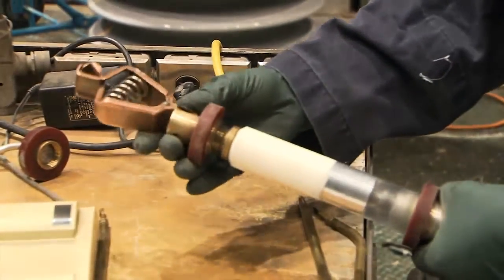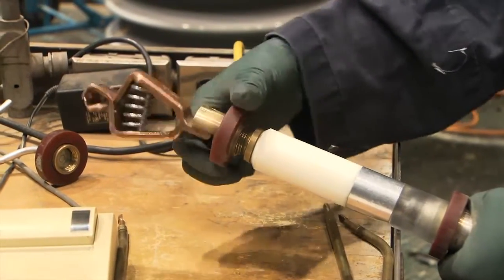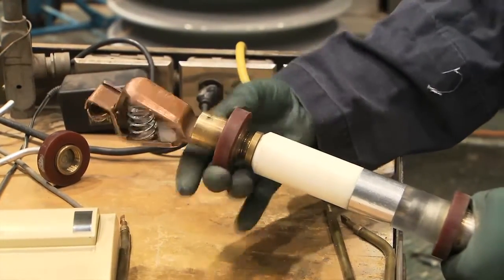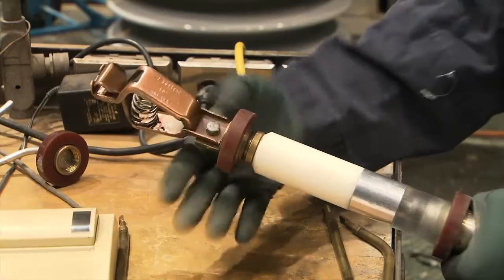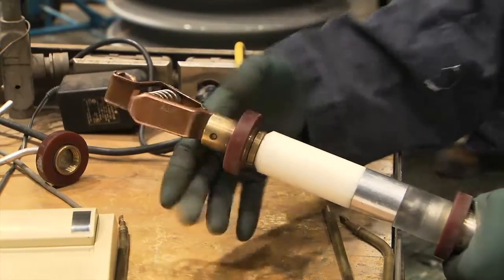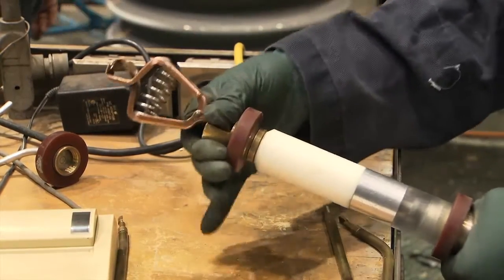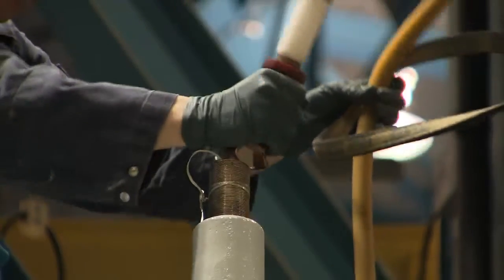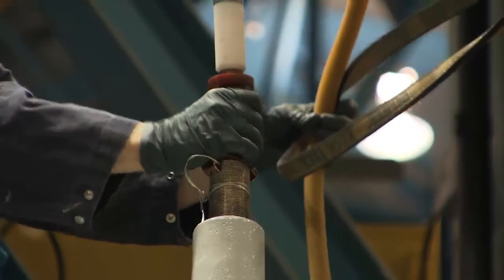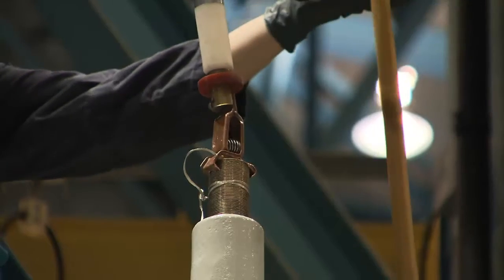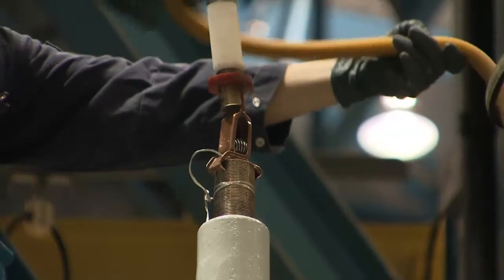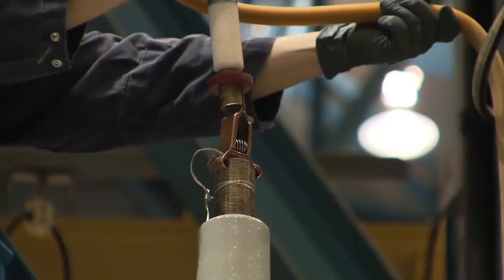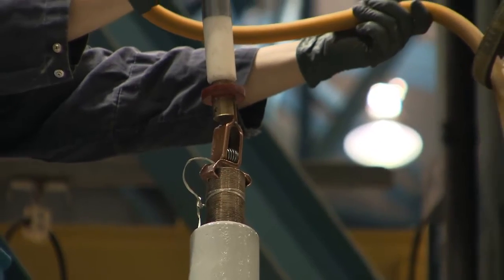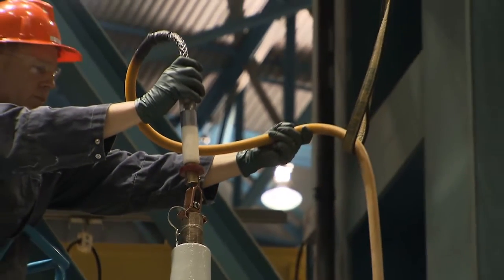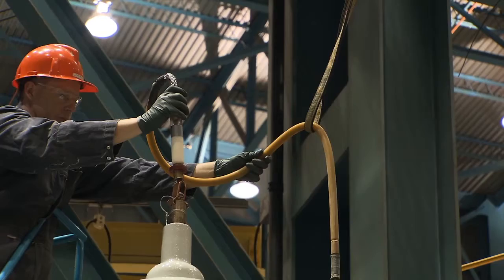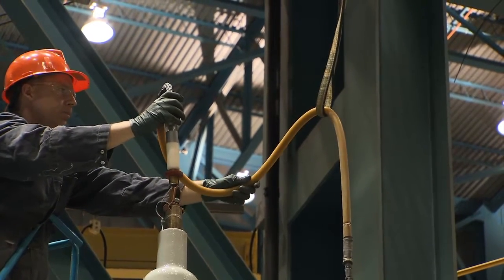Attach the connector clamp to the high voltage lead that will be connected to the top of the terminal. Connect the high voltage lead to the top of the terminal by clamping it directly onto the threaded rod. This lead will deliver 10,000 volts into the rod it's connected to during the C1 test. The cable must be supported securely on the sling suspended by the hoist hook.